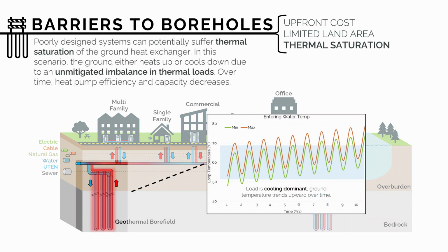Thermal saturation also happens in unbalanced loops, where the designer maybe didn't account for it, or the system changed over time. Loads got taken off the system or added, and you end up with your bore field water temperatures running away from you.